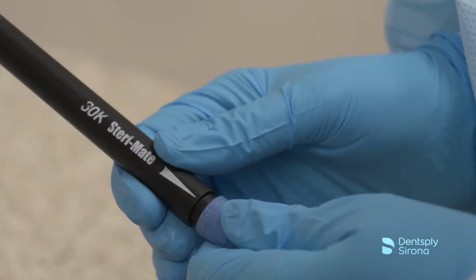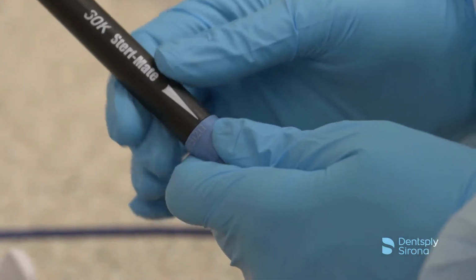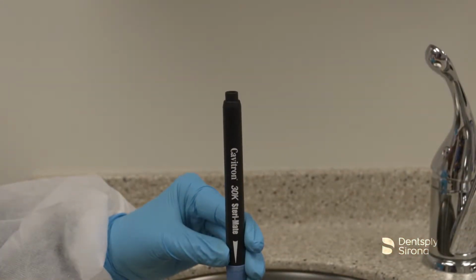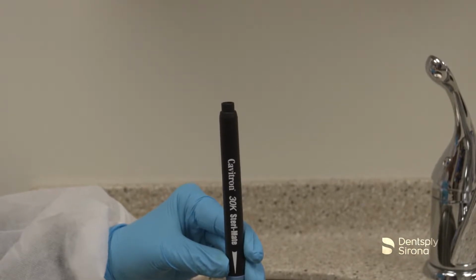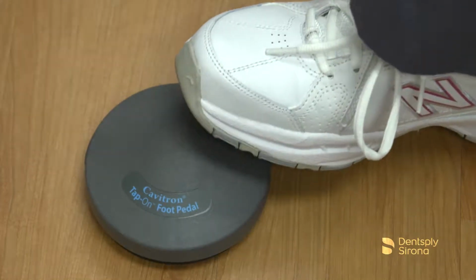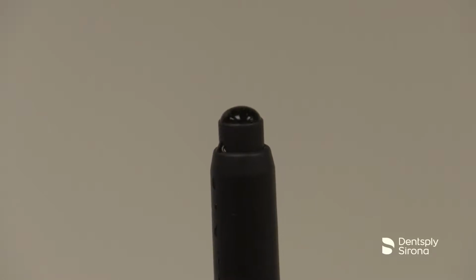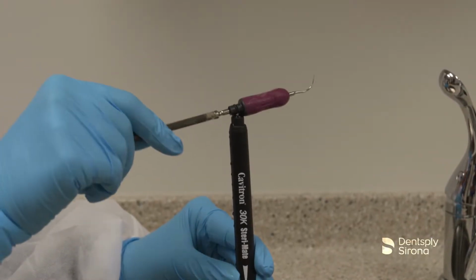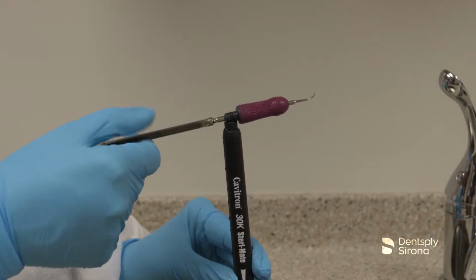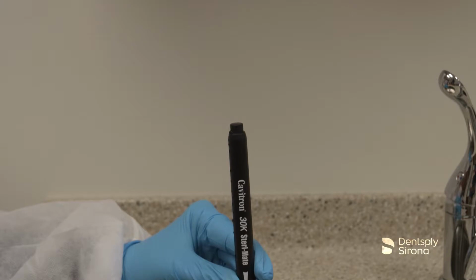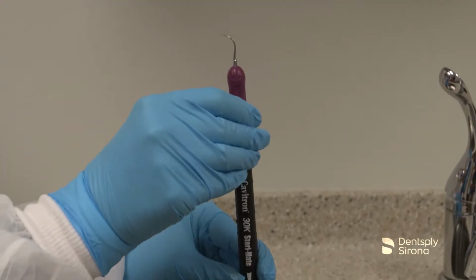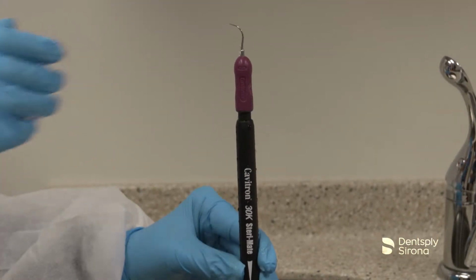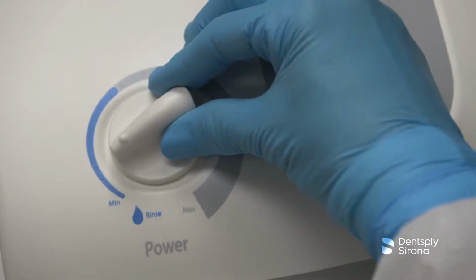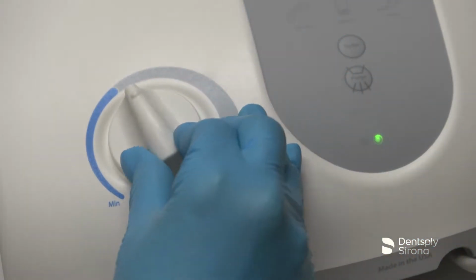To prepare the unit for another treatment session, place the sterilized Steri-Mate handpiece onto the handpiece cable assembly. Prepare the handpiece for use by holding the handpiece in a semi-upright position over a sink or drain. Depress the foot pedal until the water exits to release any air bubbles that may be trapped inside the handpiece. After opening a sterilized insert, lubricate the O-ring on the insert with water before placing it into the handpiece. Fully seat the insert with a gentle push-twist motion. Do not force the insert into place. Adjust the system controls according to the recommendations for the insert selected.